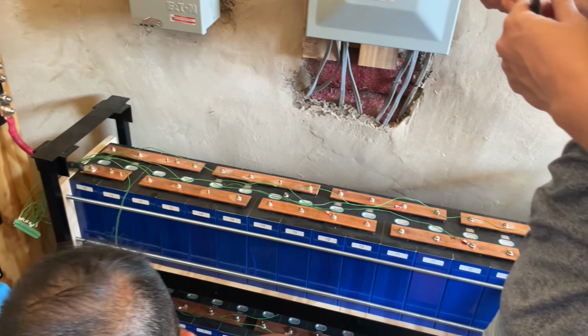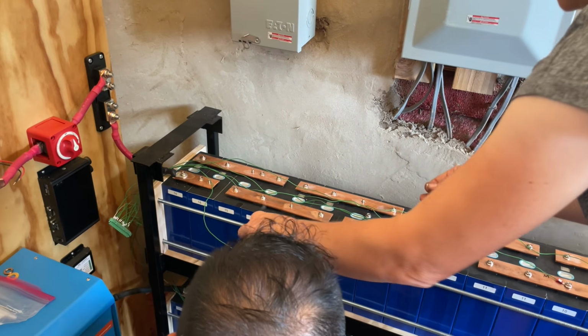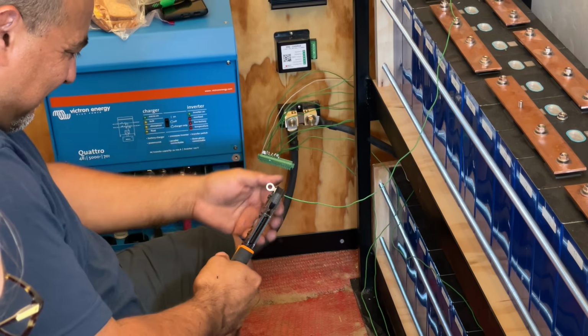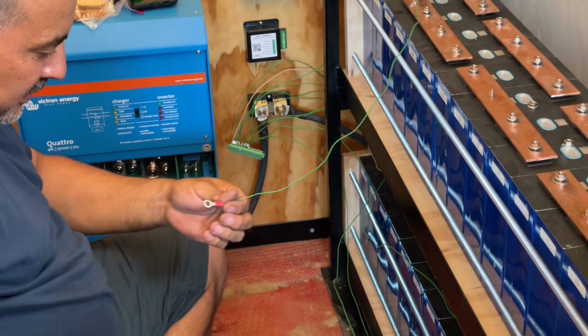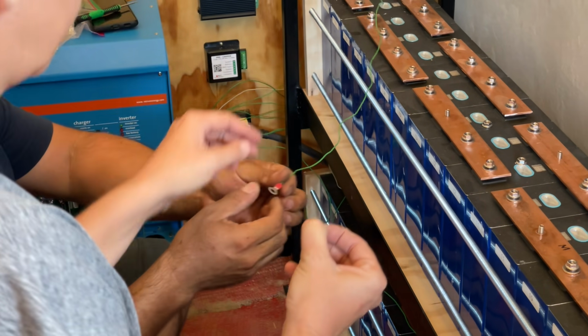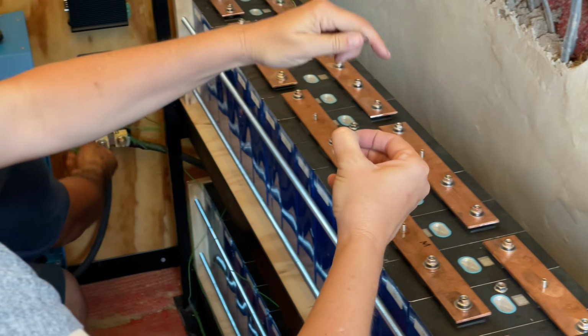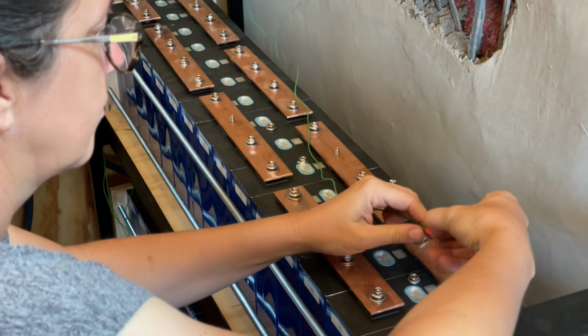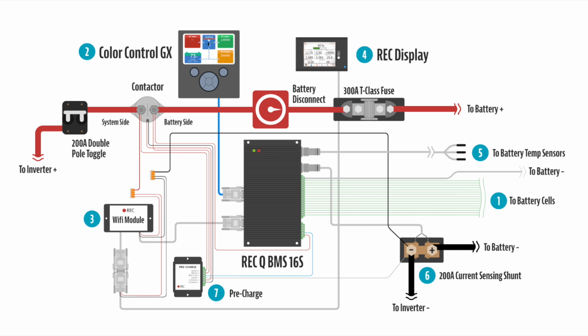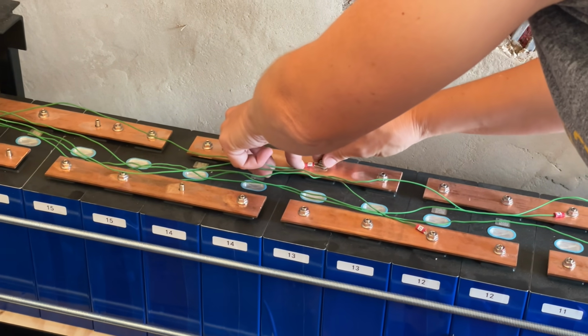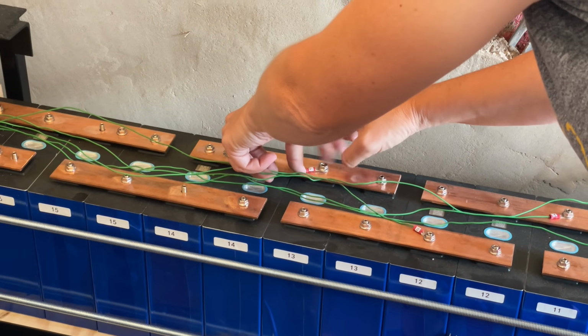Step 1: turn off the BMS, pull the cell wiring harness out, and start running individual wires from each battery cell to the corresponding number. We use small 18 gauge wire - one end goes into the screw terminal, and the other we crimped with a ring terminal to go on the positive post of the cell. Keep in mind the first input on the harness actually goes to your negative connection on the battery, then you connect to all the positives in order down the line. Do not plug this wiring harness in until later.